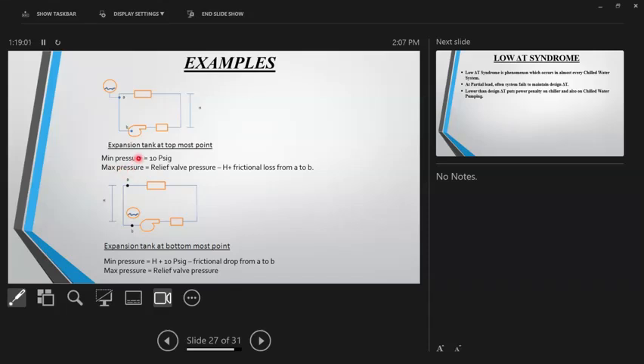Maximum pressure is what? Now the maximum pressure will happen somewhere here, right? After the pump. Now let's say PN16, or your relief valve setting pressure. So that was here. But I am concerned about the maximum pressure in the expansion tank. So what should that be?